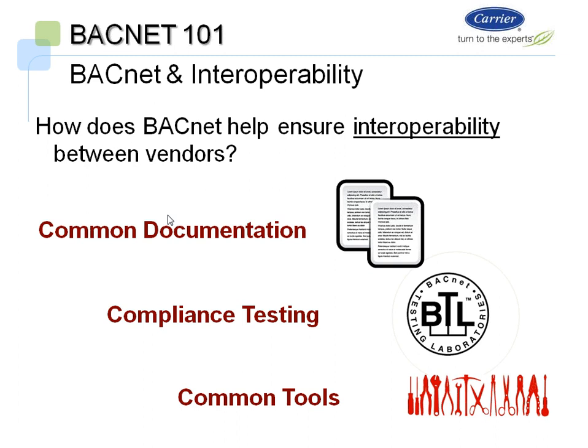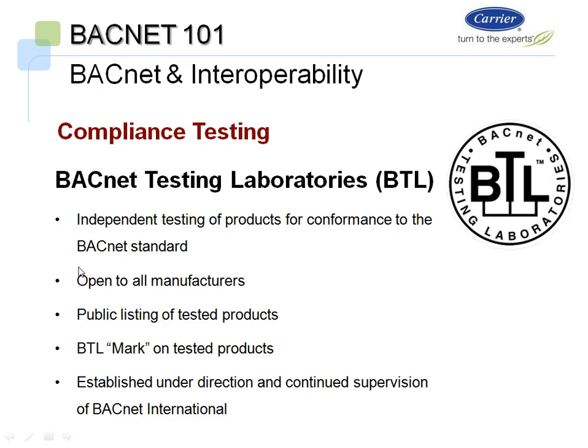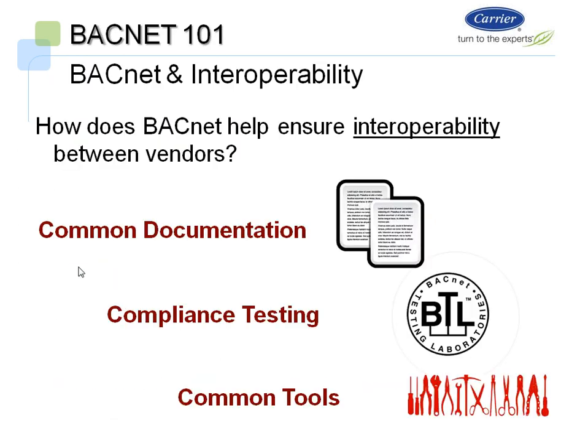So how does BACnet make its documentation, its protocol interoperable? They do publish documentation specifically for, if we go to the next slide here, oh, we lost the slide. But there are what are called PIC statements. It's protocol implementation conformance statements, and these tell you what the different control systems can communicate via BACnet, how they communicate, what accessible points they have. Most vendors do publish, if not all, their points lists so that you know how to communicate to specific points, to find different objects, what reference names you need to use, what values, what types.